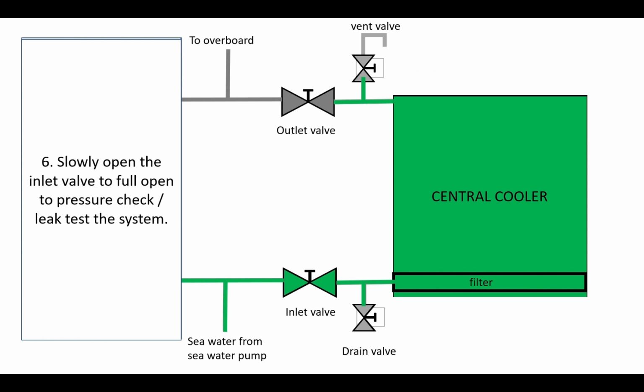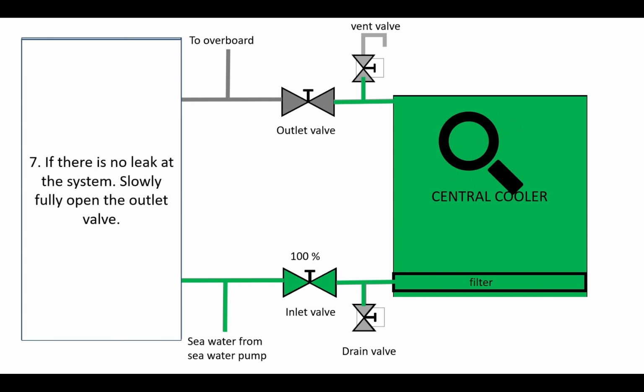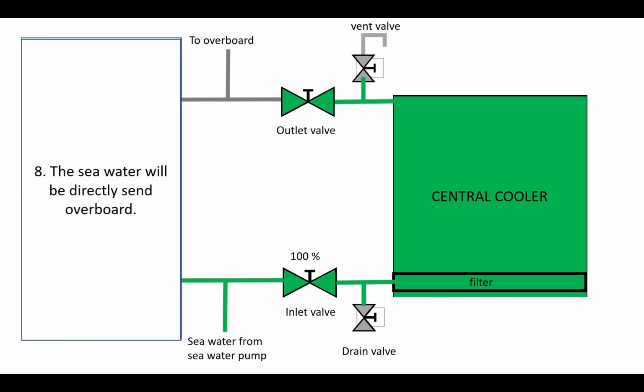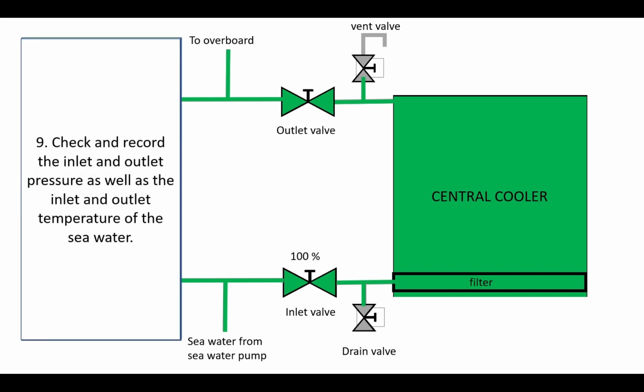Slowly open the inlet valve to full open and check the system for leaks. If there is no leak in the system, slowly open the outlet valve. The seawater will leave the cooler and be sent directly overboard. Check and record the inlet and outlet pressure as well as the inlet and outlet temperature of the cooler for maintenance reference. Now that the seawater side is filled, let's fill the fresh water side as well.